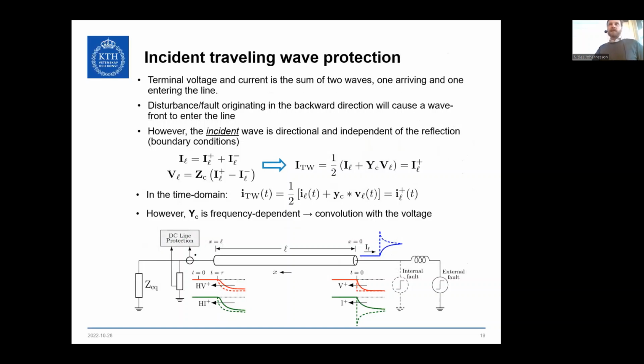Since the voltage and currents are always the sum of two waves, if you want to detect this kind of internal fault, you need to be able to differentiate something happening in the backward direction from the forward direction. What I proposed in this paper was basically to use the incident wave—so you eliminate one of the waves, and only see the one coming from the line into the terminal.